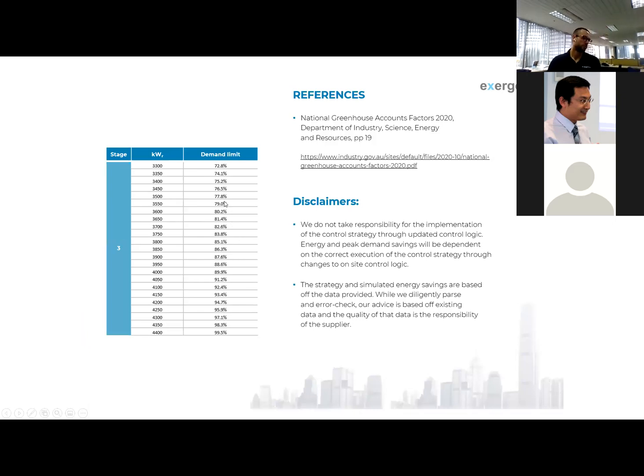So this covers all of stage 3, and on that low load chiller, we apply a demand limit based on that total refrigeration through the system. What this is trying to achieve is to say, given a certain cooling load, we should only use, for example, 72.8% of the low load chiller, so that the high load chiller is doing some percentage of the cooling that keeps both of them at their optimal point in the part load curve. Rather than trying to optimize for a single chiller, this is just looking at plant COP as a whole, and then judging how much of the load each of the chillers should be doing.